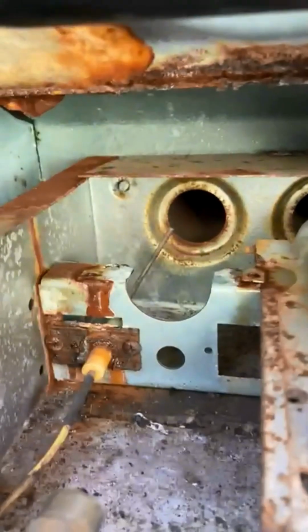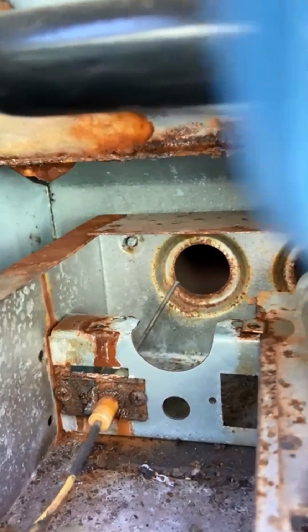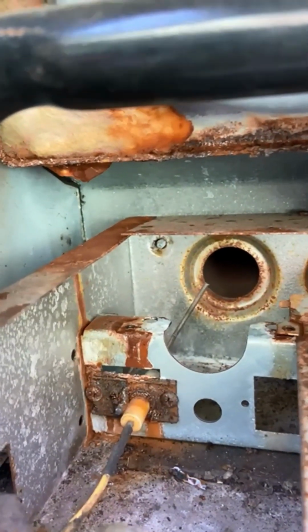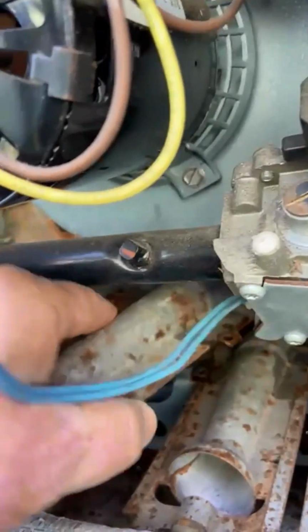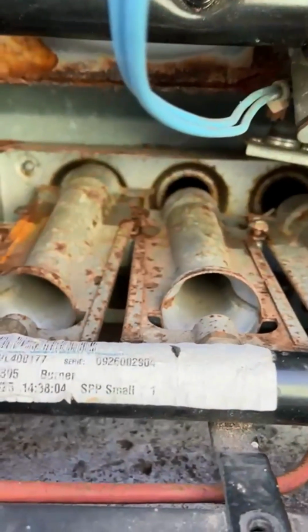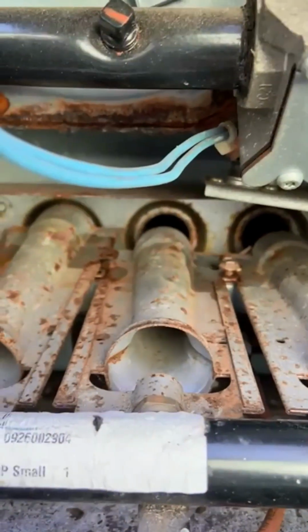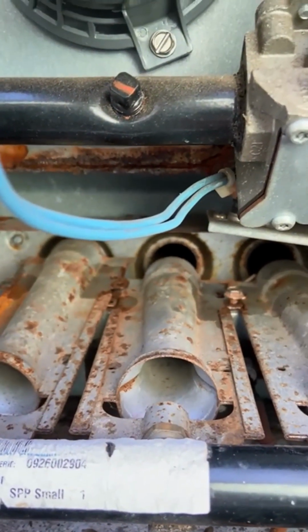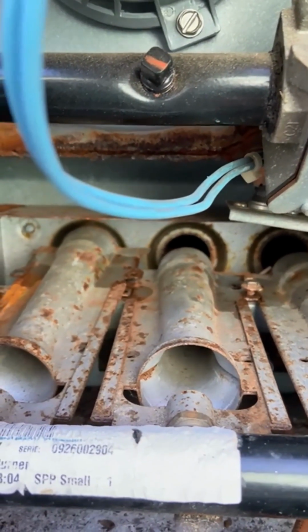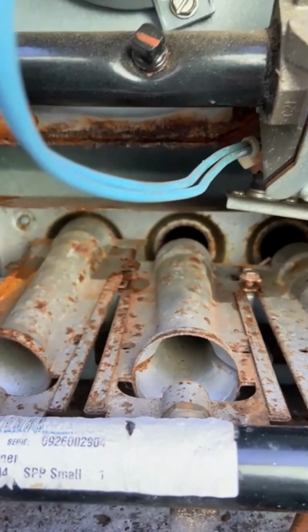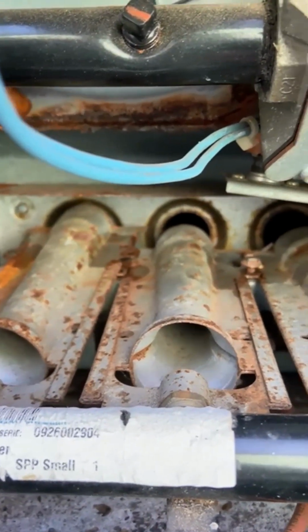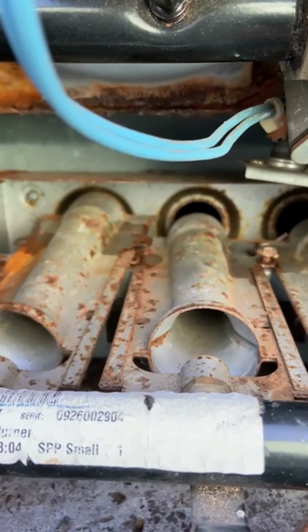Flame sensor's nice and clean now, but it wasn't picking up that flame sensor, so it would just run for 2 or 3 seconds and just keep doing that. She said it was heating sometimes, it wasn't. It would only work with the fan in the on position. That's because the unit wasn't telling the fan to come on, because it wasn't detecting a flame. But I got them all out and cleaned up, and it's firing up real good now.